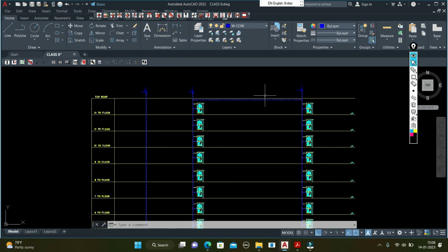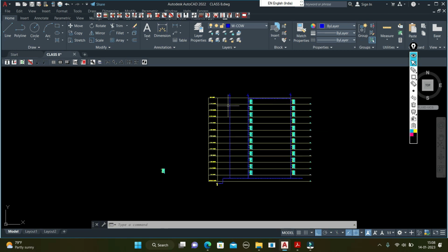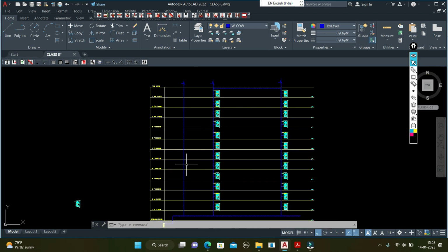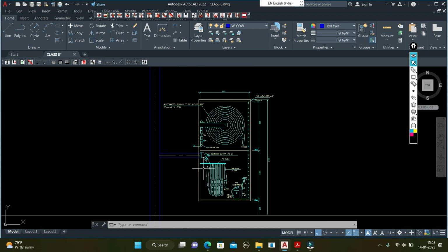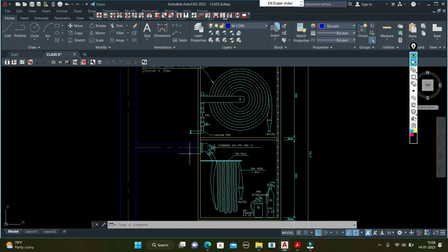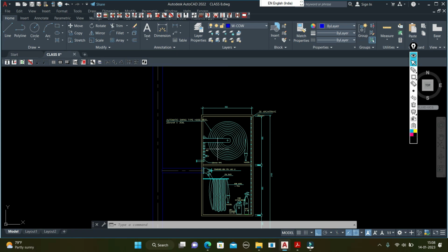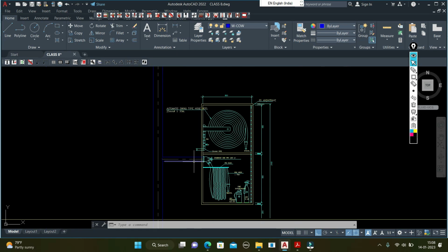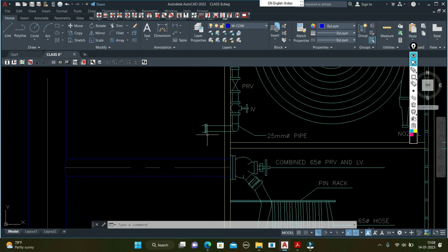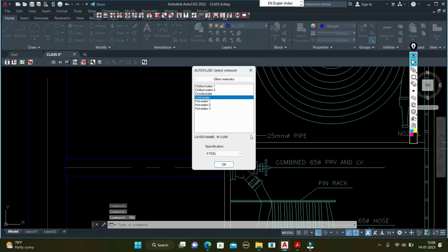Okay, it should be interconnected, but also this riser we take for the sprinkler system. Okay, this one riser is connected to the landing valve and the hose reel. Because for hose reel we can connect like this. See, either it's a size 40 or 25.